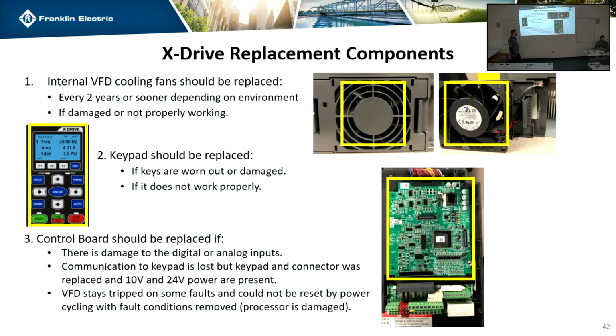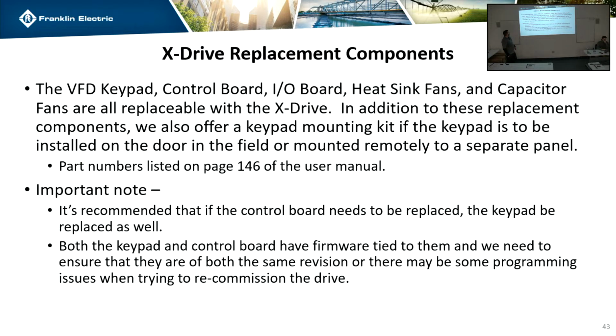One of the cool things is that when you replace the control board, it is separate from the I/O board, so all of your wires don't have to come out. You basically unscrew this thing, snap it down, the control board comes out, put the new control board in, snap it up, and you're done. There's no wiring, it's just the screws. Heatsink fans and capacitor fans are all replaceable.